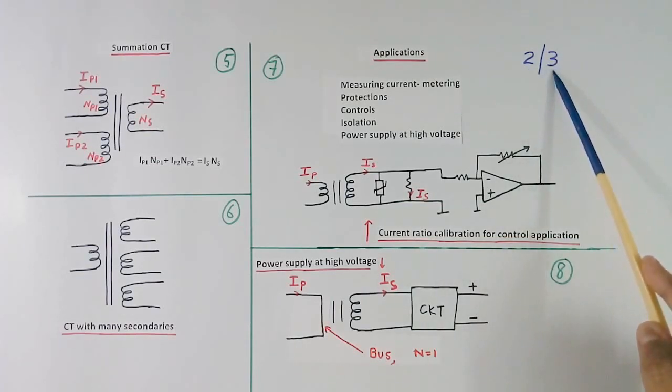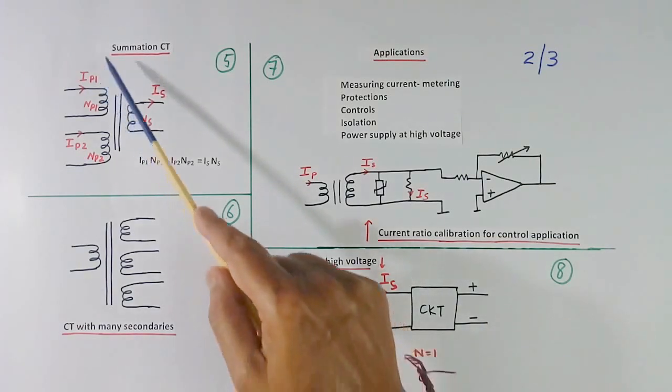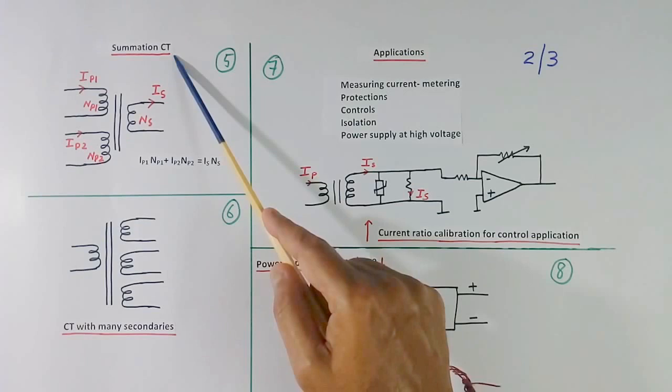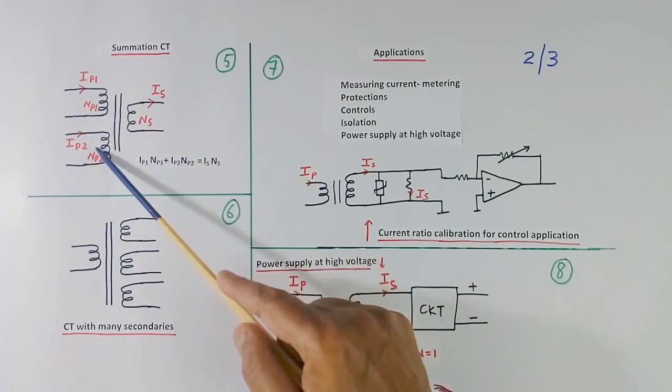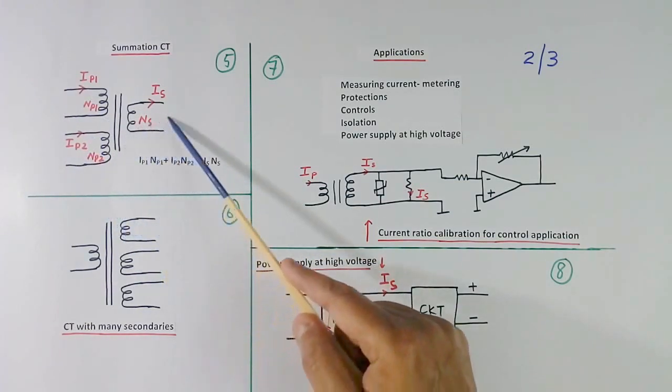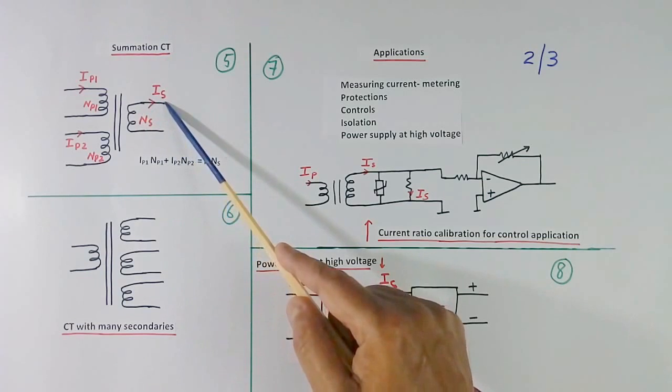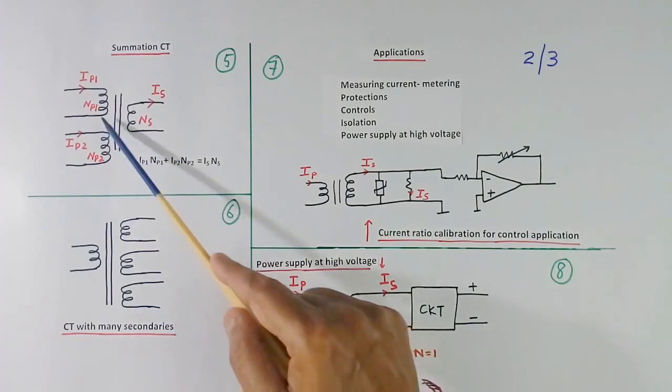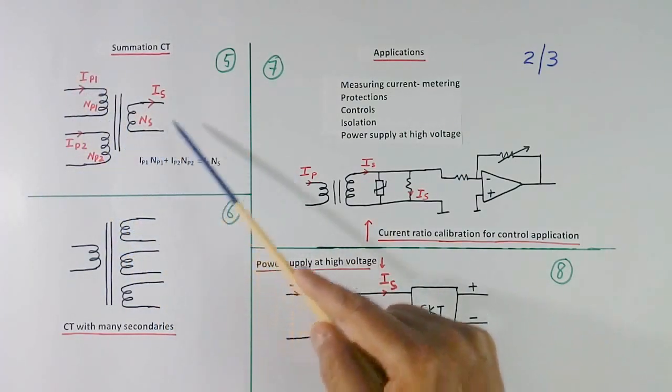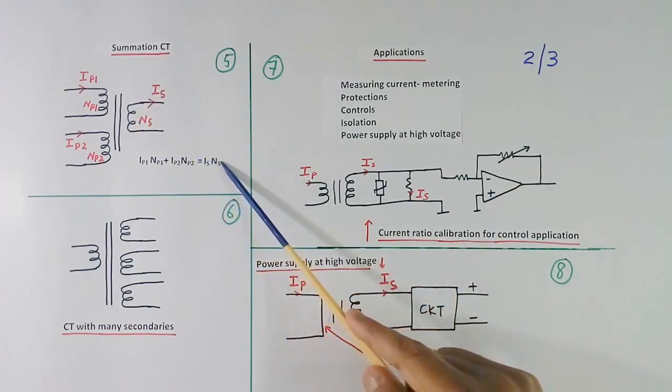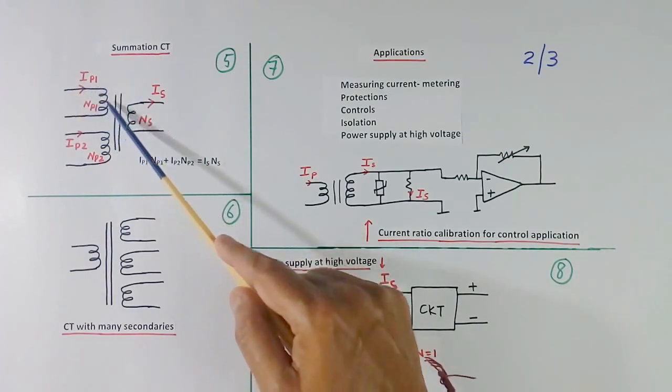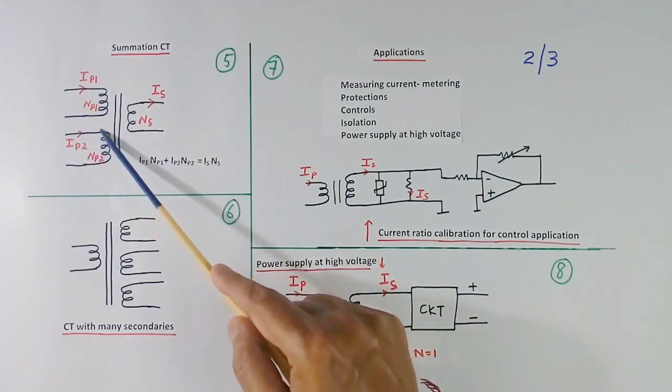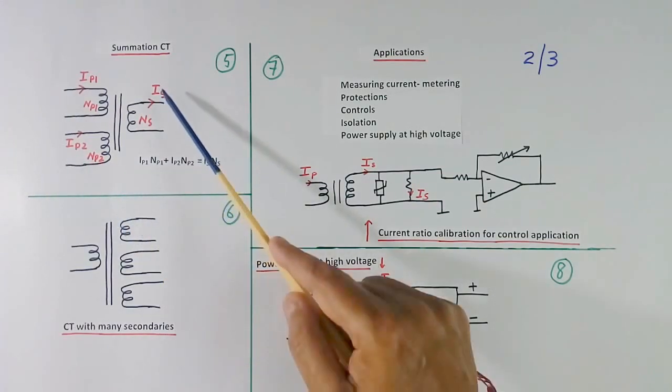This is second sheet of theory. So far we were talking about normal typical CT. But there are summation CT available. This CT will have many primary. Here I have shown 2. There may be more than 2. And secondary will be 1. And secondary current will show the summation of all currents. And ampere turn of total primary will be equal to ampere turn of secondary. Like here, IP1 into NP1 plus IP2 into NP2 is equal to IS NS.